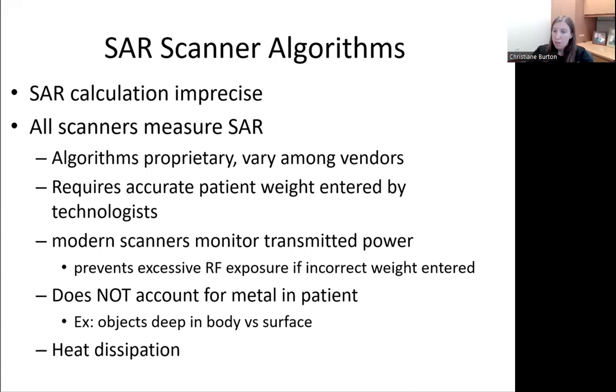SAR measurements are displayed on the scanner. The calculation of SAR in human subjects is very complicated and imprecise, and it requires sophisticated mathematical modeling and computer simulations to estimate it. All commercially available MR scanners have programs that estimate SAR values automatically when a specific imaging protocol is selected, and warn the operator if regulatory limits are likely to be exceeded. However, each manufacturer uses a different proprietary algorithm, so the calculated SAR values may differ substantially among vendors. To get a reasonable estimate for SAR requires an accurate patient weight to be entered by the technologist.